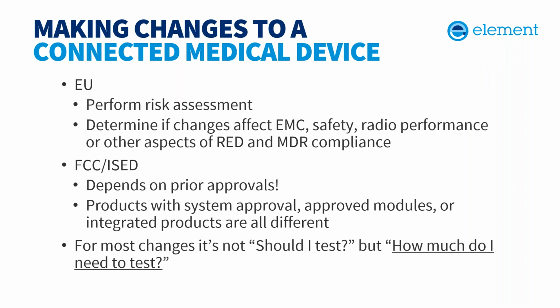So if you change a power supply for the host, that's pretty much a full retest for a medical device for -1, -2. But if you have a large system with many pieces and you change one piece of that large system, you might not need to do full testing. This is something you definitely should reach out to your local test lab to discuss and see what will make sense. So the next step is evaluate how does this change the radio portion of the product.